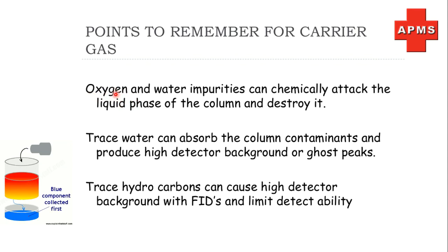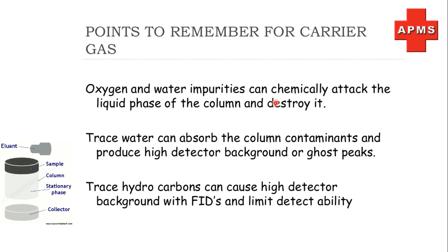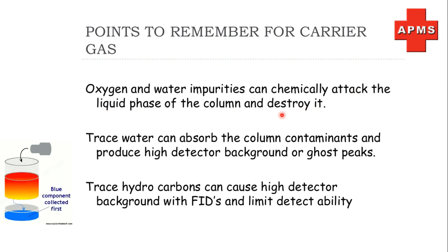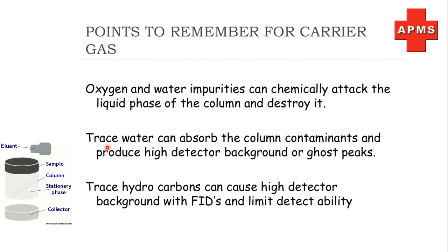So if any oxygen or water impurities are present in the carrier gas or the sample, then at elevated temperature in the column, these impurities can attack or react with the liquid phase of the column and destroy it. So the carrier gas and even the sample should be oxygen and water free. A trace of water can absorb the column contaminants and produce high detector background or ghost peaks.